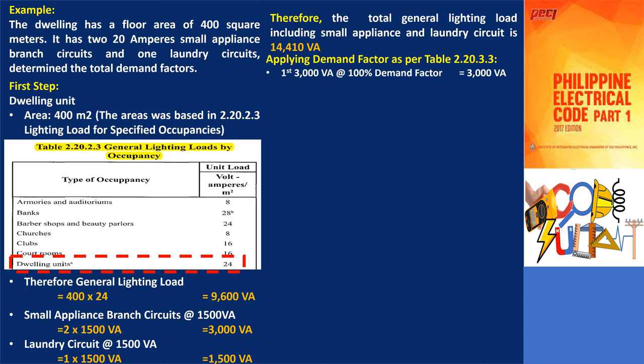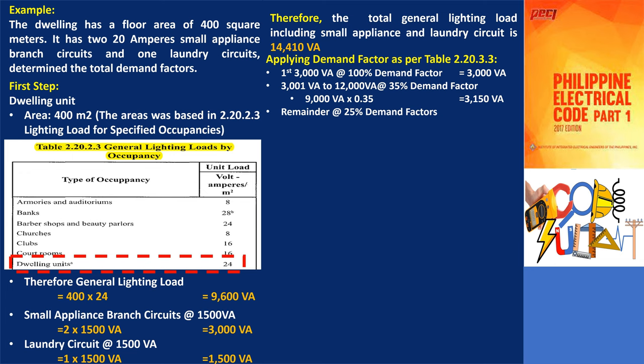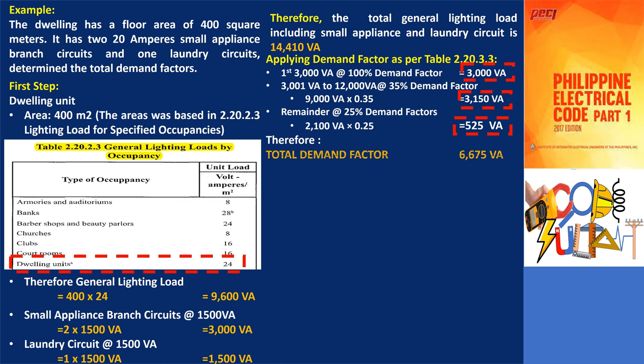Apply the demand factor based on table 2.20.3.3. The first 3,000 volt amperes are at 100% demand factor. The range from 3,001 to 12,000 volt amperes is at 35% — 9,000 VA times 0.35 gives 3,150 VA. The remaining volt amperes from 12,001 to 14,410 are at 25% demand factor — 2,100 VA times 0.25 equals 525 VA. The total demand is 3,000 plus 3,150 plus 525, therefore the total demand factor for general lighting load in this example is 6,675 volt amperes.